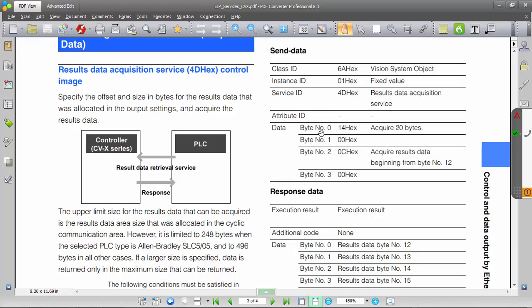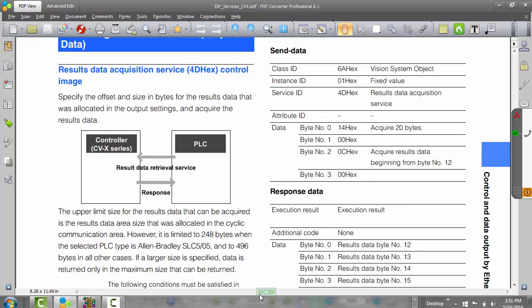Basically, how this works is we're going to send 4 bytes of information. In bytes 0 and 1, you're going to tell it how many bytes to acquire — that's 4 bytes for every data output item that you set up. So if you have 6 items, it's 6 times 4, which is 24 bytes. The receive amount depends on how many items you're receiving, which is set up on the CVX side. You can also optionally put an offset in bytes 2 and 3 if you want to skip some of the results.